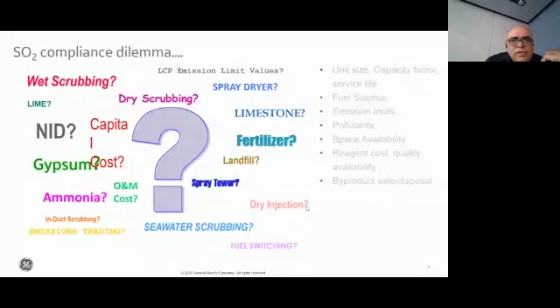Yeah. So today when we look at India, we are looking at primarily wet FGD solutions for large power plants, 500 megawatt plus. Semi-dry FGD when we are talking about smaller plants, and seawater FGD if it's a coastal and an open cycle seawater based cooling water plant. So in that case, we would go in for seawater FGD, but otherwise we will go in for open spray tower with wet FGD and limestone as the reagent.